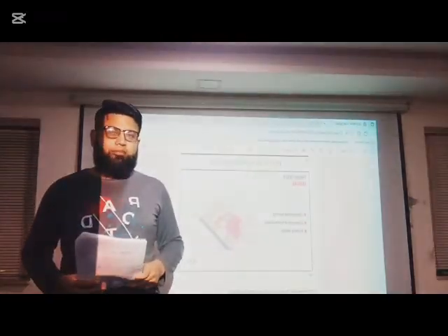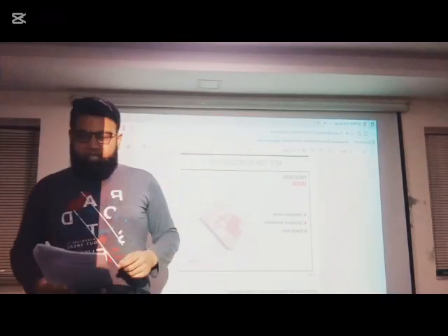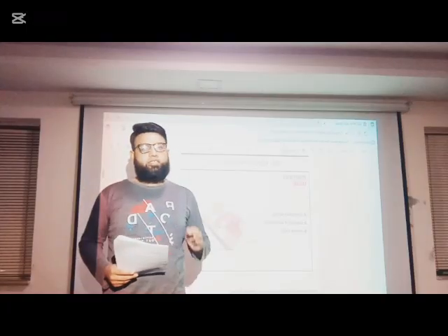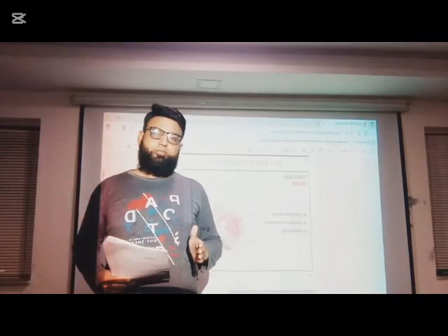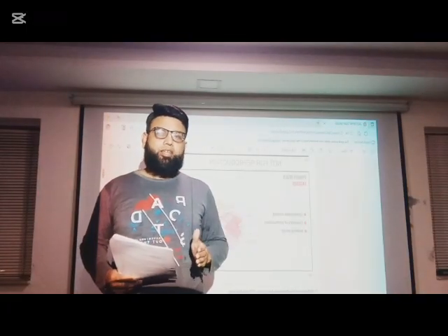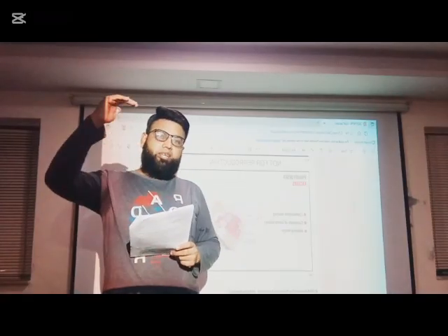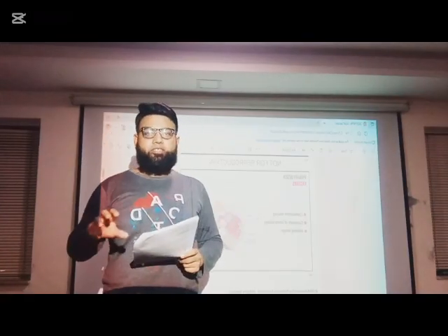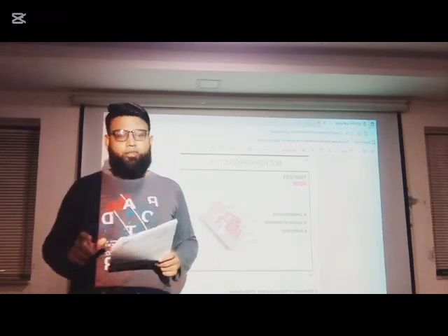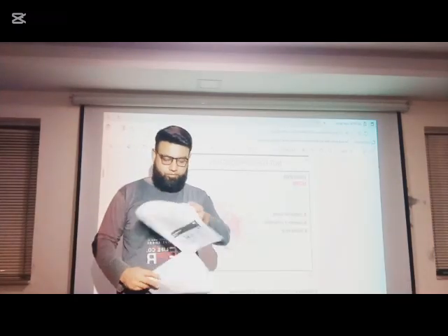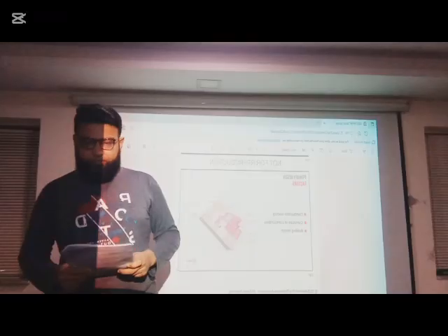The third component is the building design. Building design means the ceiling height. The ceiling height will determine the placement of the sprinkler systems, the spacing between them, and the area of application for the sprinklers. The higher the roof, the more the spacing will reduce, and all such decisions will be taken as per the building design.